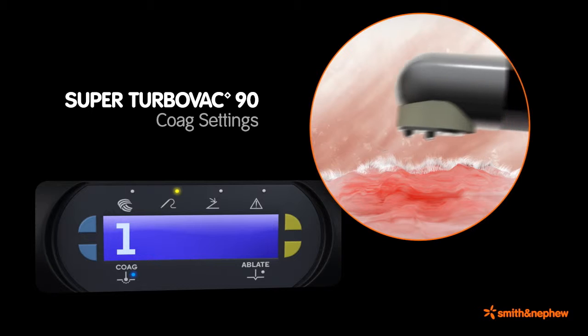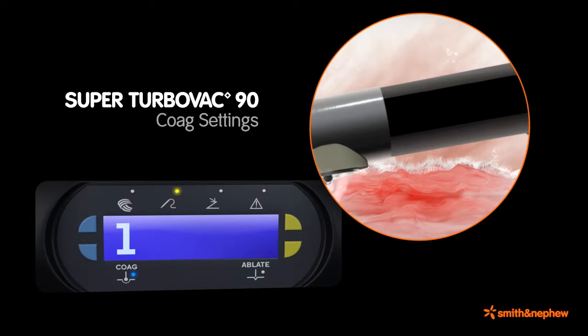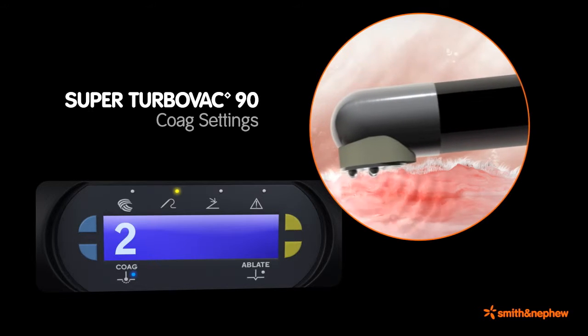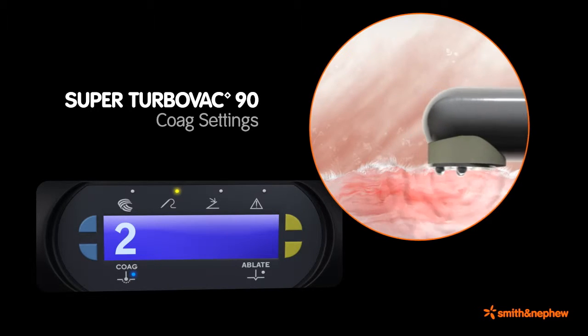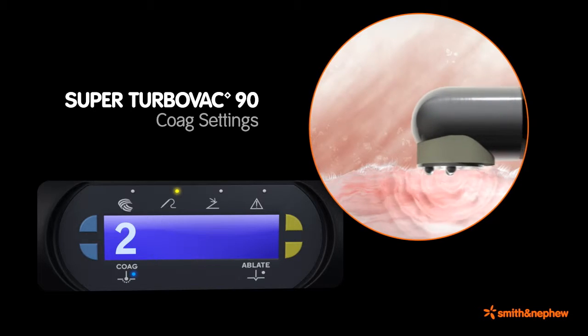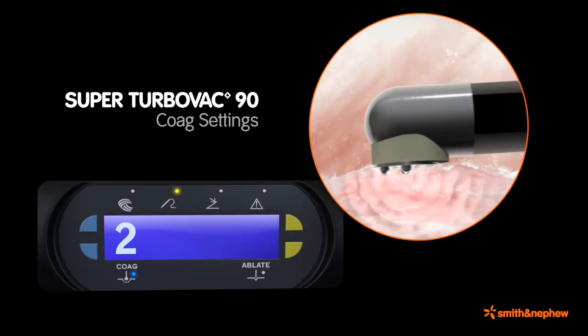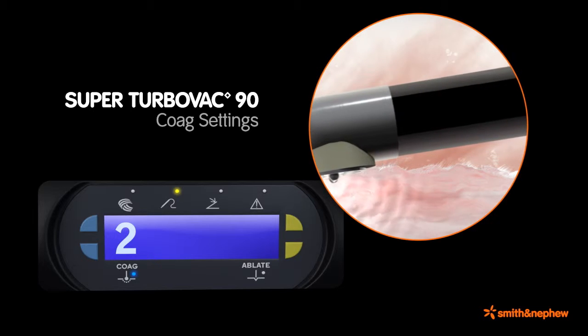All coblation wands can operate in coag mode for hemostasis. At lower settings, with minimal formation of plasma and its insulation, the current flows through the tissue. Blood vessels within the tissue are coagulated, stopping their bleeding during a surgical procedure.